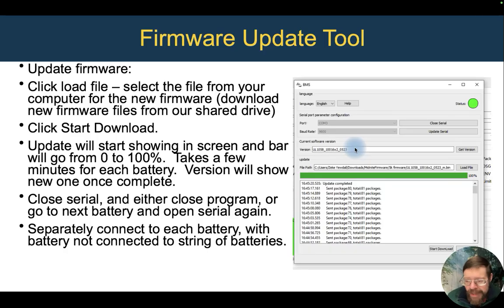If you've got a whole bunch of batteries, the newest ones may be able to be updated all at once, but most of the older batteries... and it's just usually better practice to do this for all of them: disconnect all of the batteries and update them one at a time, connecting to each one, updating it, and disconnecting and moving to the next one, and then reconnect all the battery comm cables and put it back together in a whole bank.